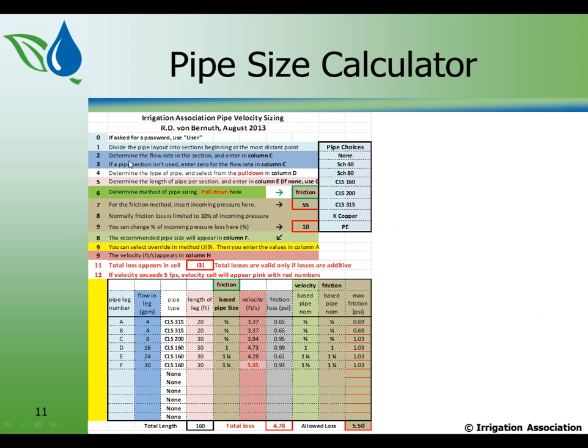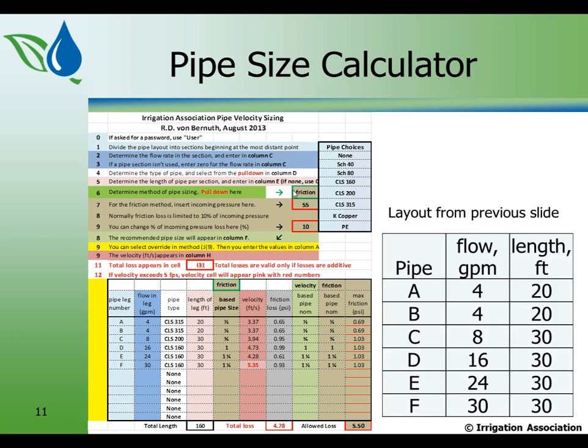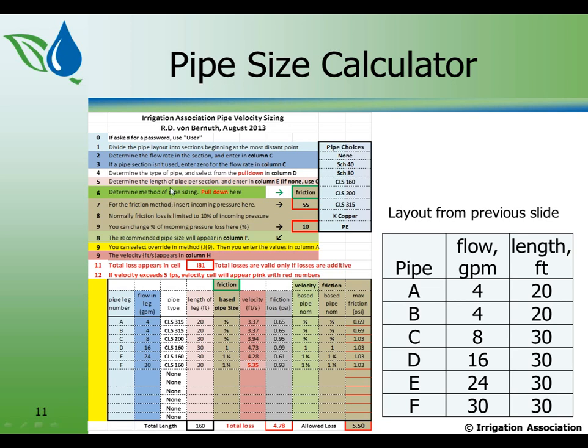Step one, divide the pipe layout into sections beginning at the most distant point, which we've done. Determine the flow rate in each section and enter those in column C. We've determined the flow rates and they've already been entered for you in column C. And I've reproduced that layout from the previous slide here on the right. So you can see that pipe A right here is pipe A right here, and it is four gallons a minute, and it's 20 feet long. If you don't use a pipe section, enter zero for the flow rate in column C. This is column C. You would enter zero and then nothing else shows up because it's formatted that way.